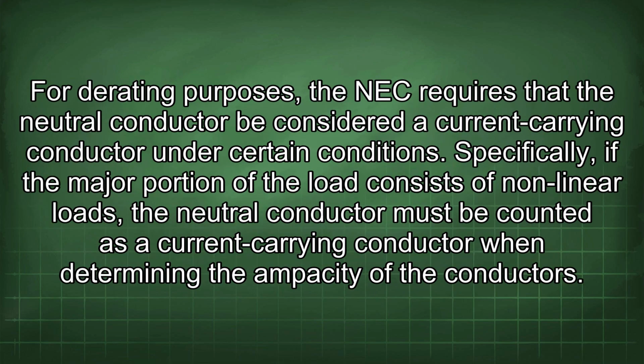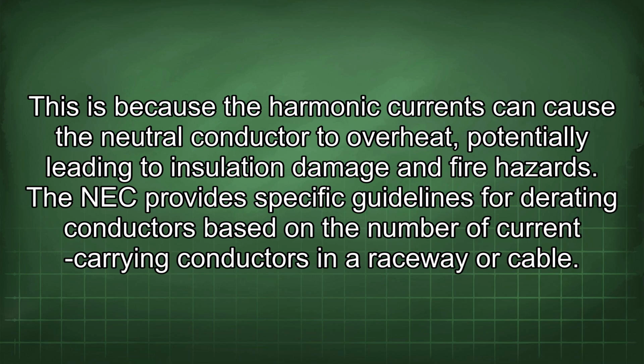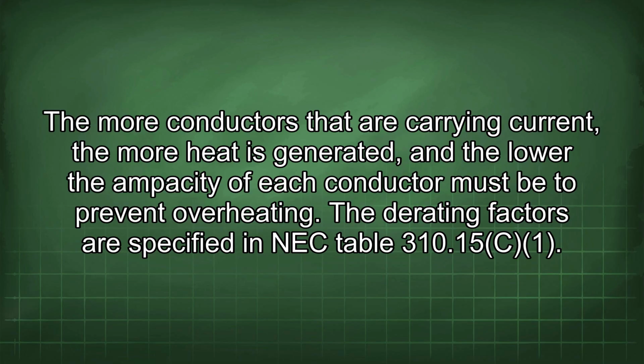For derating purposes, the NEC requires that the neutral conductor be considered a current-carrying conductor under certain conditions. Specifically, if the major portion of the load consists of nonlinear loads, the neutral conductor must be counted as a current-carrying conductor when determining the ampacity of the conductors. This is because the harmonic currents can cause the neutral conductor to overheat, potentially leading to insulation damage and fire hazards. The NEC provides specific guidelines for derating conductors based on the number of current-carrying conductors in a raceway or cable. The more conductors that are carrying current, the more heat is generated, and the lower the ampacity of each conductor must be to prevent overheating. The derating factors are specified in NEC Table 310.15.